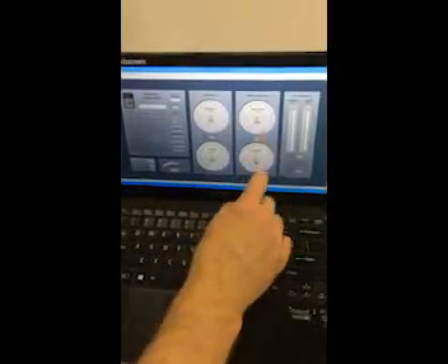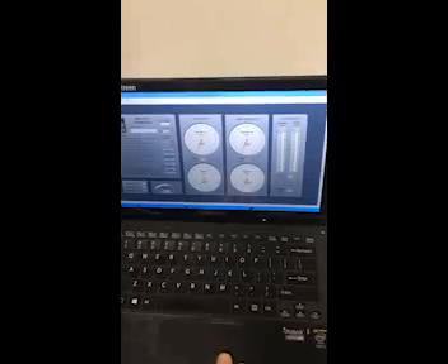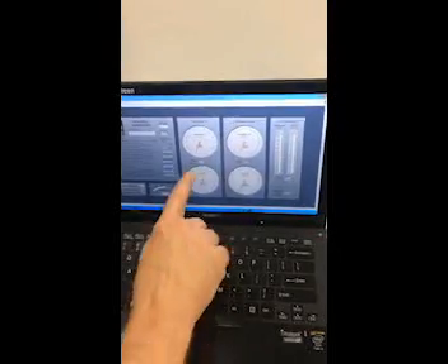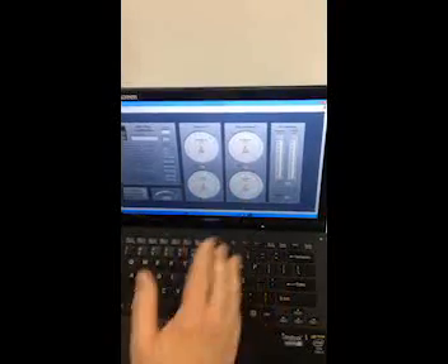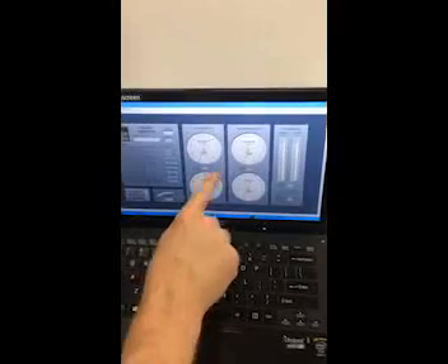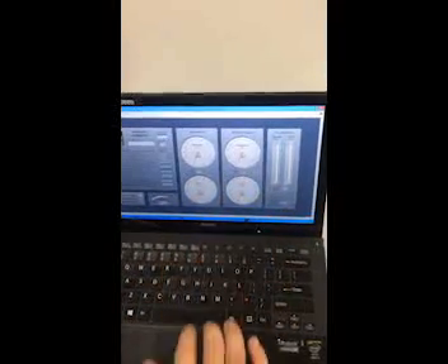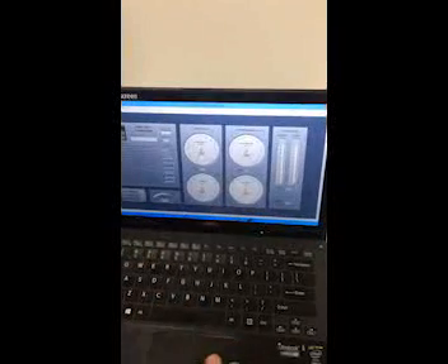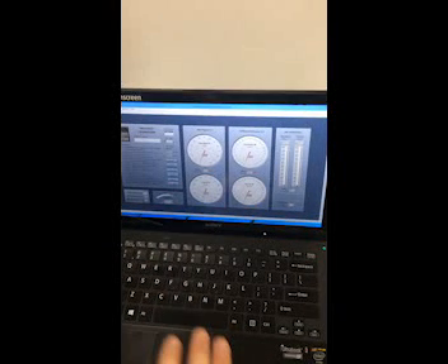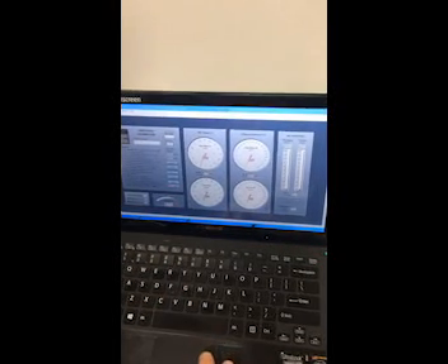Okay, at this point we've pressed the calibrate pressure. You know that it's done correctly if these two gauges match each other, the flow meter dP and the test set dP. Now, since they are calibrated, should be matching one another. Another thing you want to look for is that you should have 3 green lights, meaning you've encountered no errors. This light, and this light. All 3 will match green. If one of them is red, we need to go back and do steps again. If all 3 are green, that means we're ready to generate the report.